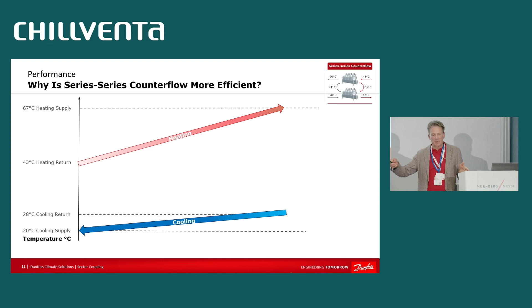That higher differential within the heating system itself—not from cooling to heating, but within the heating system—creates the opportunity to split the load into two circuits. A literal example is our own data center at our headquarters in Nordborg, which has a 43°C heating return and 67°C heating supply.